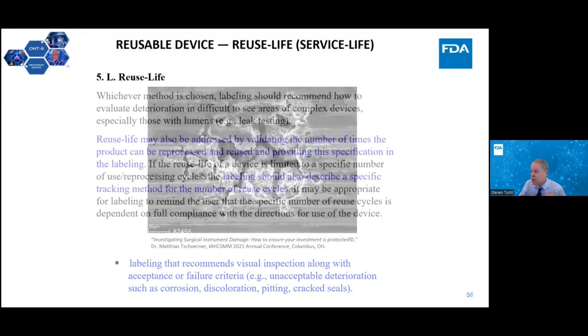And the very end of this is, whichever method is chosen, labeling should recommend how to evaluate deterioration in difficult to see areas of complex devices, especially those with lumens. Reuse life may also be addressed by validating the number of times the product can be reprocessed and reused, and providing this specification in the labeling. So we already did cover that. Labeling should also describe a specific tracking method for the number of reuse cycles. So for that robotic arm that has 10 use cycle lives on it, they provide a method for the end user to track the number of times, so 10 is not exceeded. So that's all I have on stability for medical devices.